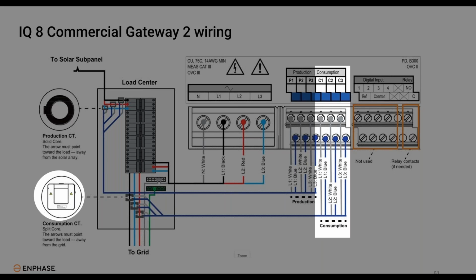The consumption CTs will wire into the 3 ports to the right of the production CTs, line 1 to line 3. The consumption CTs are not required for your site. The only thing that is required are the production CTs.